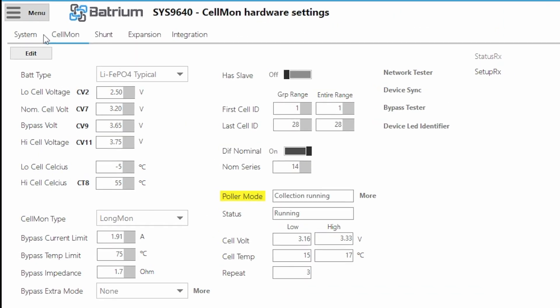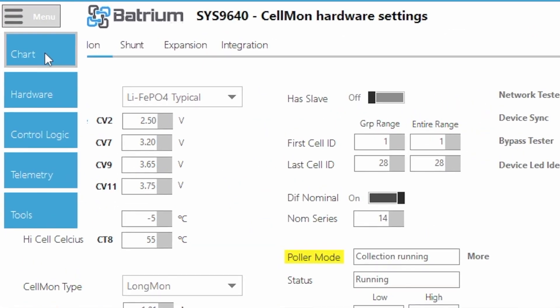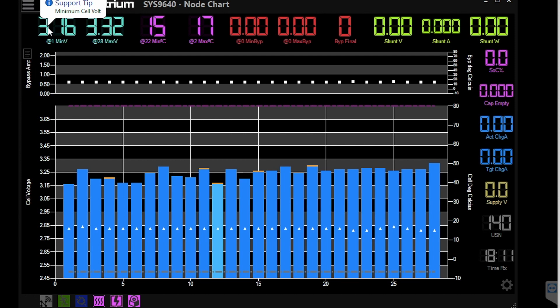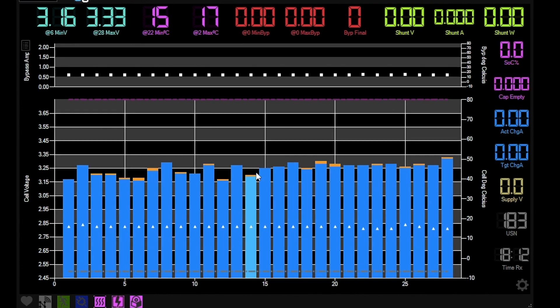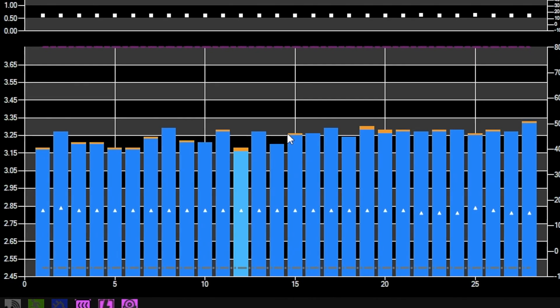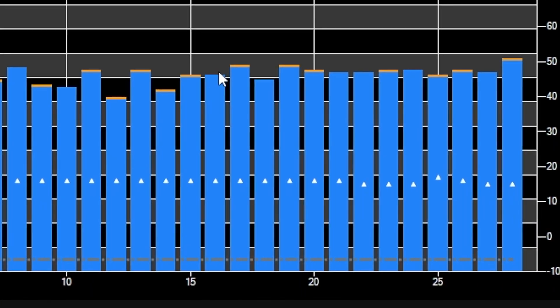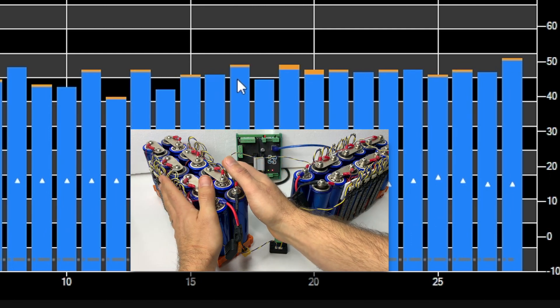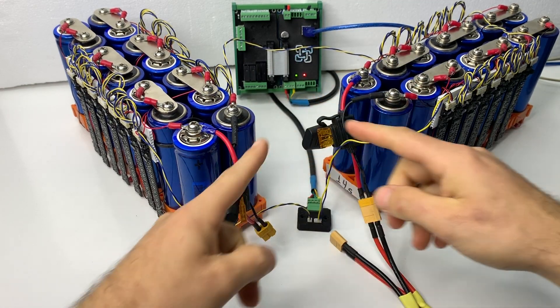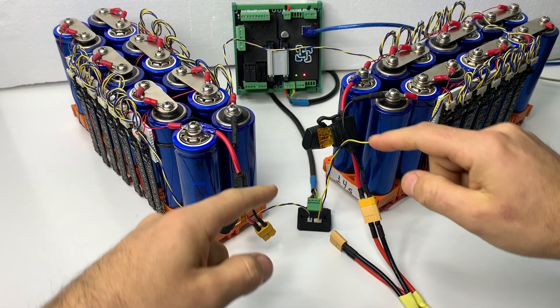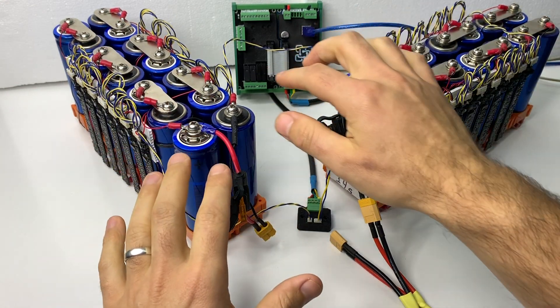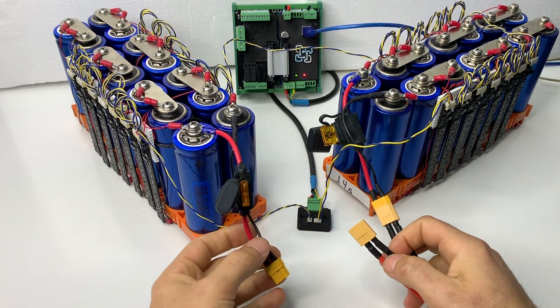You close the tab and let's check if it's working now. So now I have 28 cell monitors running through the same WatchMon supervisor, two packs. So you see here up to 14 is one pack. So then from the 15 series all the way to the last one here, 28, is actually the second pack. So now the watch mode supervisors see all 28 cell monitors talking properly, connected properly, configured properly. So now it's time to parallel both battery packs together.